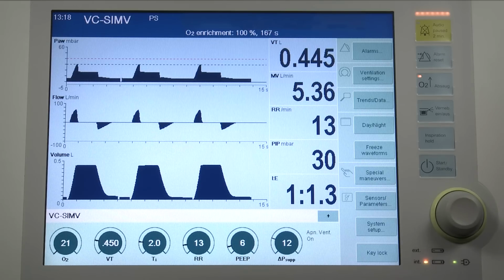In the header bar, the initial oxygen enrichment phase is displayed with the remaining time. Disconnect the patient and perform the suction maneuver. 120 seconds are available for suctioning. In the header bar, the disconnection phase is displayed with the remaining time. Afterwards, reconnect the patient. Savina 300 continues ventilating in the set ventilation mode, except that for 120 seconds, 100% O2 is delivered for final oxygen enrichment.